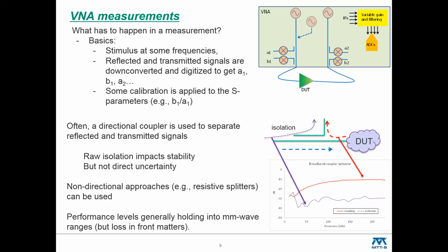You may be very familiar with this kind of block diagram, where there's one or more stimulus sources, usually just a sinusoid, maybe switched, there may just be lots of sources. Some signal separation devices to pull off incident, reflected, and transmitted signals. Some down converters to generate these A and B waves that can be digitized. And then some calibration is applied to take out loss in cables, mismatch in the VNA itself, and other variables.